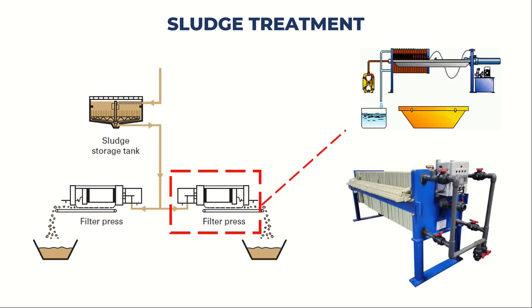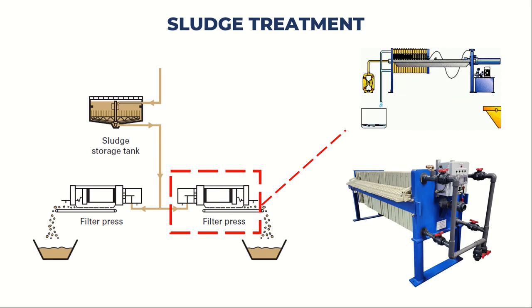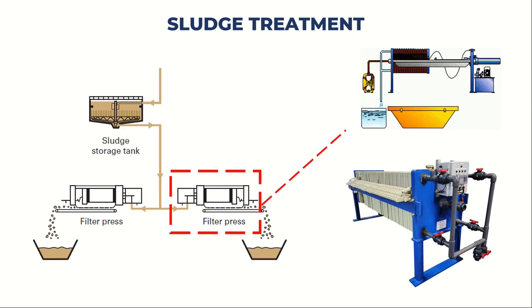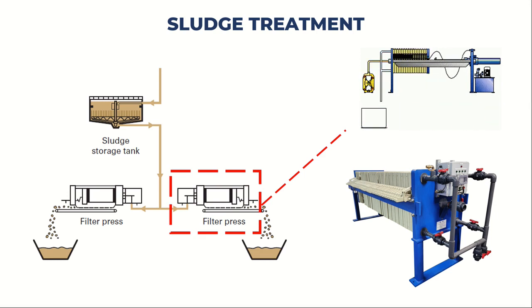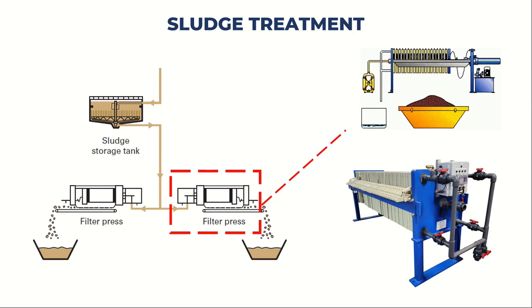Next, we have the filter press. This equipment is used to dewater the sludge by applying mechanical pressure. The sludge is pumped into the filter press, and as the plates come together, excess water is forced out through the filter cloth, resulting in a cake-like sludge with a higher solids content.